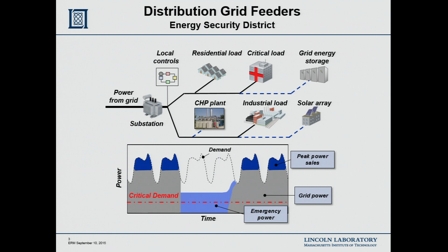You could also put a solar array on the roof — I'm not sure if this building actually has one, but it might. Then you could imagine coupling the output from the PV to the output of the CHP and combining that into a localized grid, just for this building. When you do something like that, you essentially detach from the grid at large — the transmission and generation systems elsewhere, like the 4 nuclear plants, or the coal and natural gas plants in New England — you wouldn't be able to see those. That's what we call a microgrid, and a microgrid is kind of what Boston wants to do moving forward over the next 50 years or so.